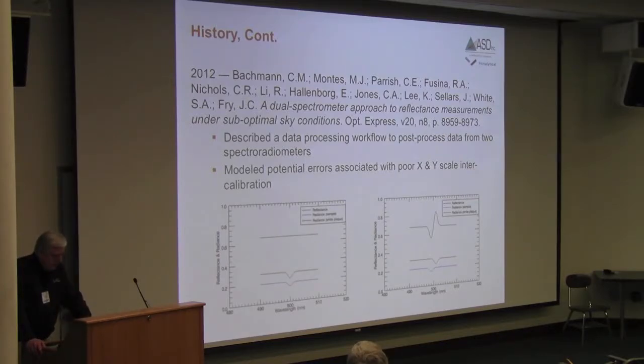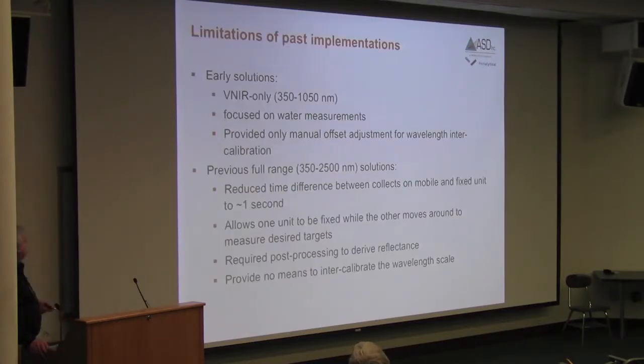If you go back and look at the earlier versions that have been done, this early solution was VNIR only, it didn't go out beyond 1,000 nanometers. And partially that was based on cost. To actually build an instrument that had 2 full-range spectrometers in it starts to get really expensive. It was focused on water measurements, and it only had this manual method of wavelength intercalibration.